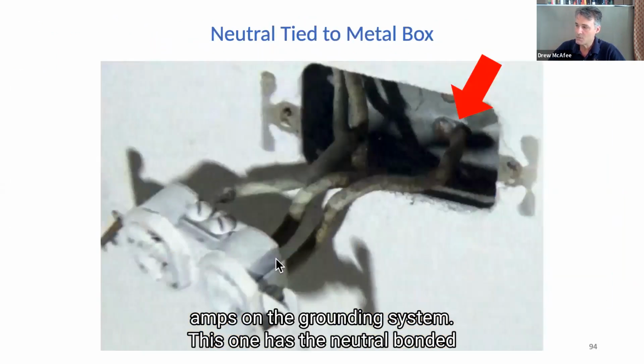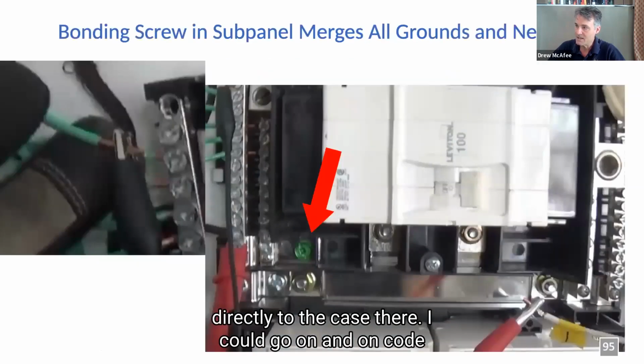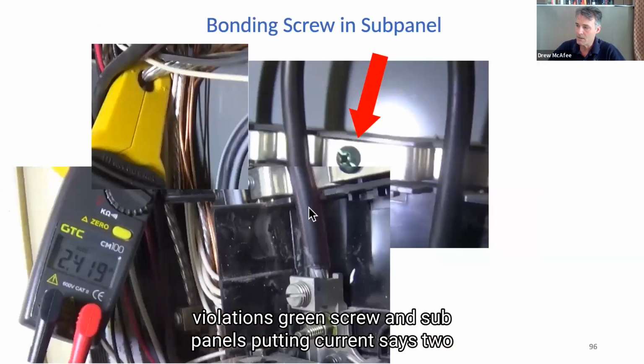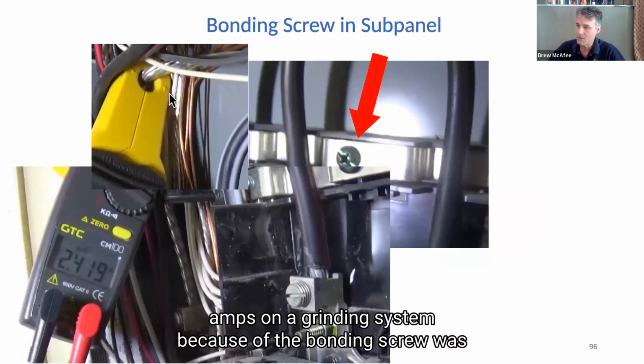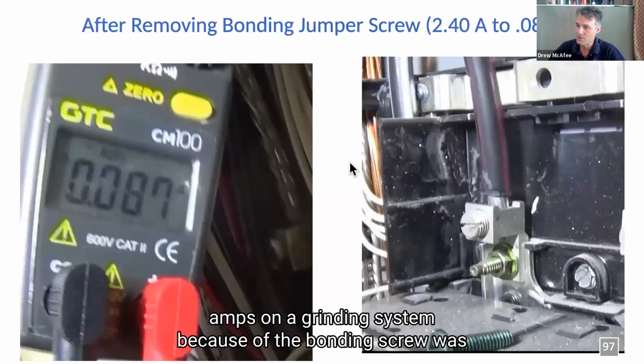This one has the neutral bonded directly to the case there. I could go on and on. Code violations: green screw in sub panels putting current. This one says 2 amps on a grounding system because the bonding screw was left in. We took it out and it went down to 0.08.